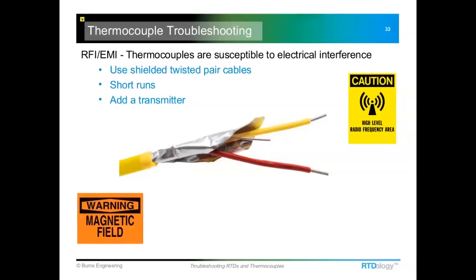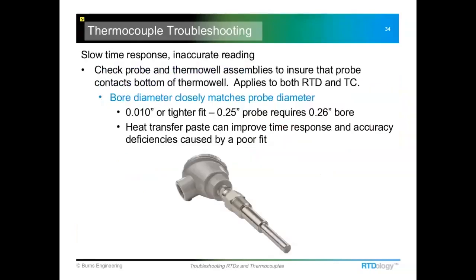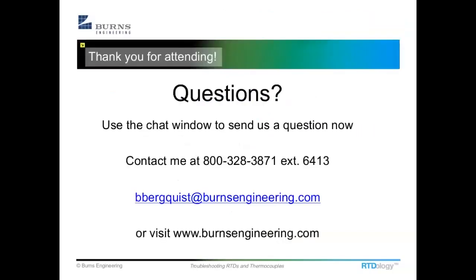RFI and EMI are really important for thermocouples — use a shielded cable. There's probably never a case where using an unshielded cable is even acceptable; they're just so susceptible to these kinds of issues. Regarding time response: thermocouples do respond faster than RTDs, but there are ways to build them for either a faster or slower response time.